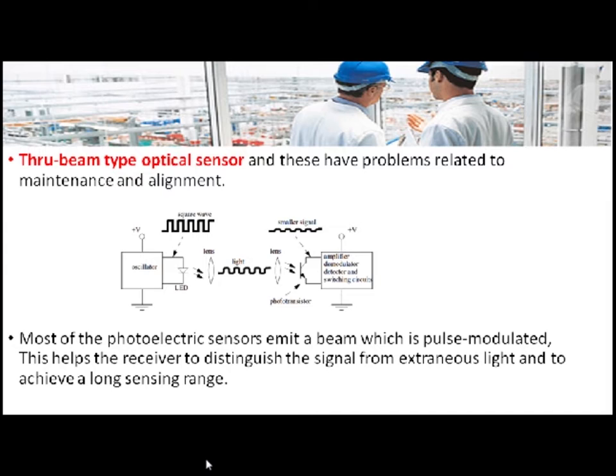In through beam type optical sensor, it consists of a separate source and separate detector assembly. The disadvantage with this type is that as there are separate modules, the alignment will be difficult and also the maintenance. In almost all optical type sensors, the light emitted from the source is a modulated signal instead of a DC signal.